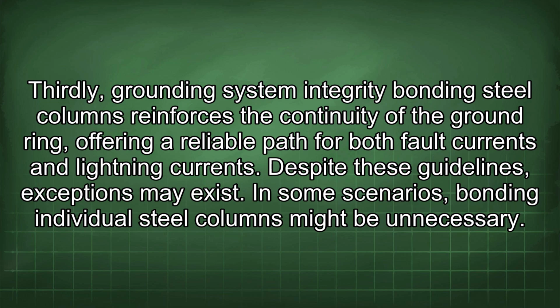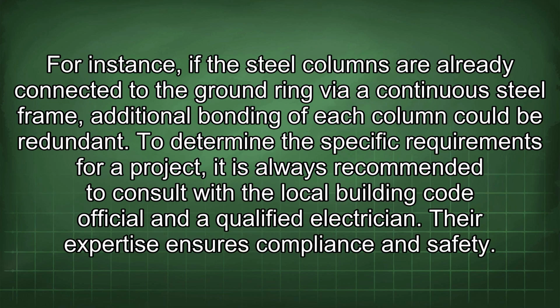Despite these guidelines, exceptions may exist. In some scenarios, bonding individual steel columns might be unnecessary. For instance, if the steel columns are already connected to the ground ring via a continuous steel frame, additional bonding of each column could be redundant. To determine the specific requirements for a project, it is always recommended to consult with a local building code official and a qualified electrician. Their expertise ensures compliance and safety.